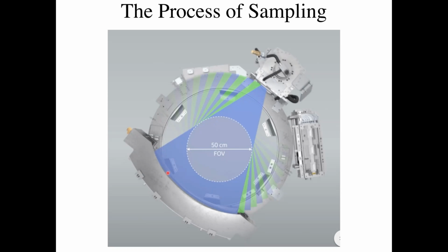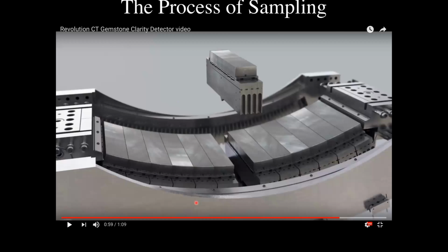And our detector element is this thing down here, okay? That whole thing's going to spin. When you take this cover and the skins off the detector itself, this is what it looks like. This is from a GE website. You can look at all of the movies associated with this thing. It's a really cool website. So along this way is theta, or this is right-left if the patient is lying in the scanner. This direction is the head-to-toe direction, or the Z direction, it's usually called.